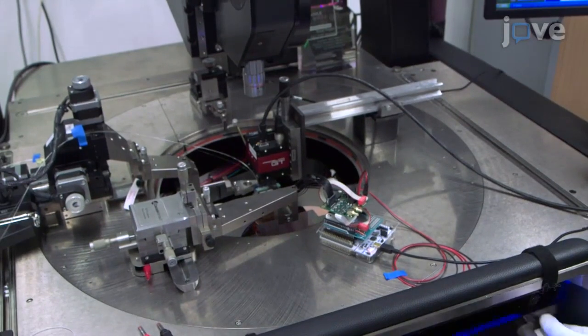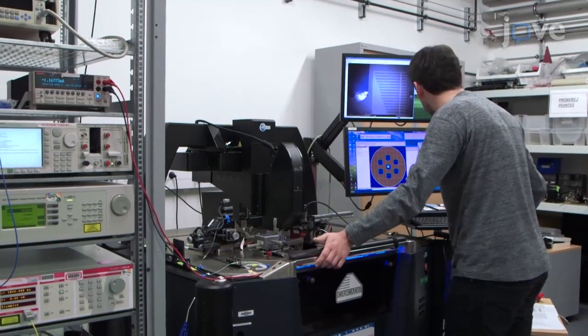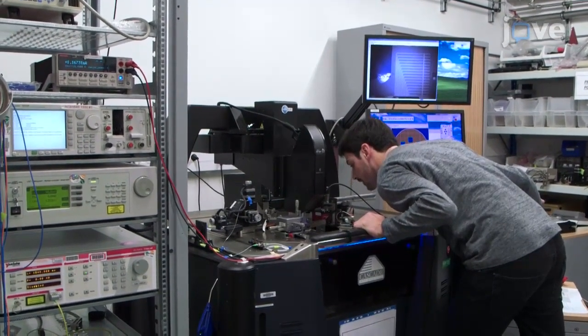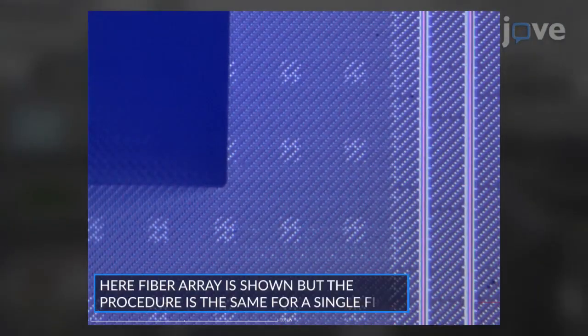To align the fibers, use a light microscope to carefully lower the fiber until it touches the wafer surface away from the input grating coupler, before moving the fiber up about 20 micrometers.